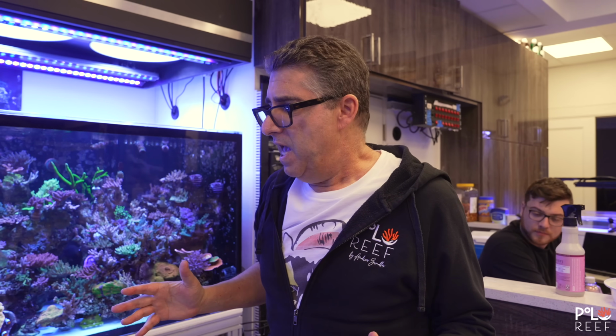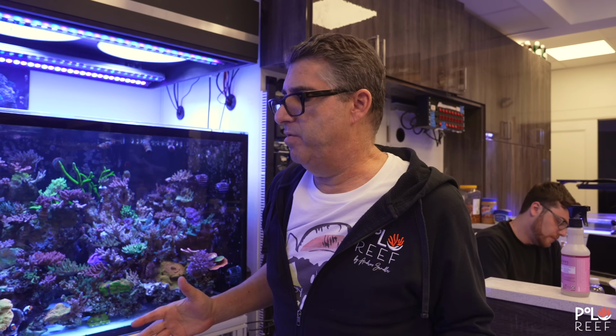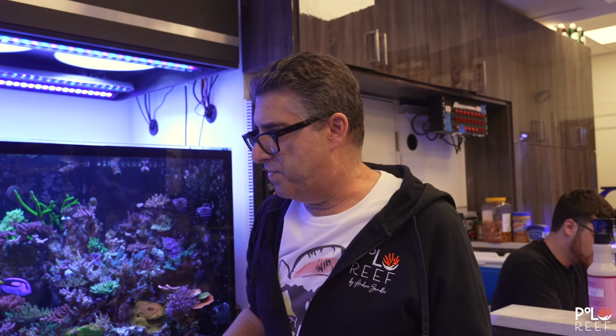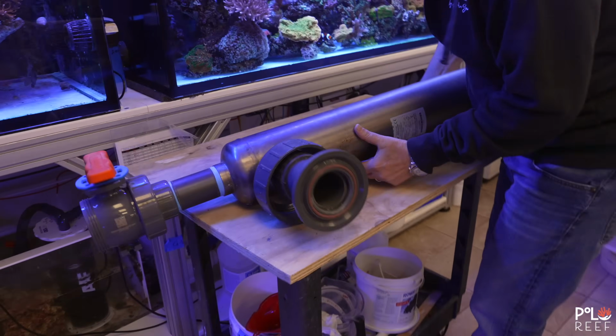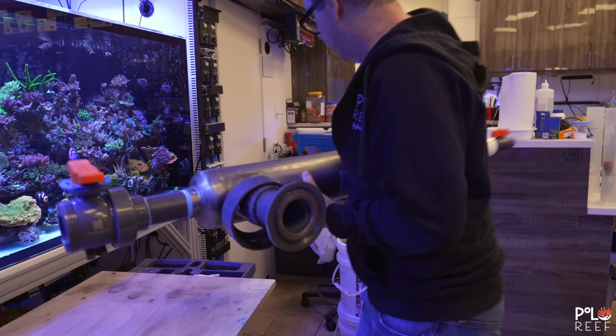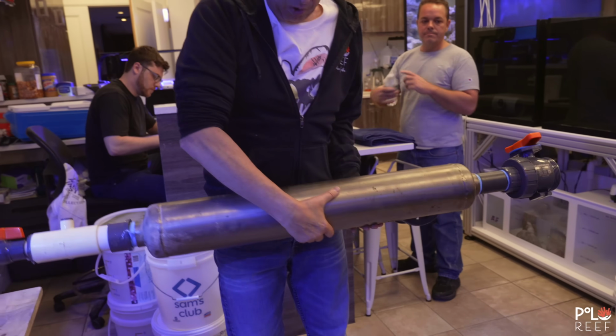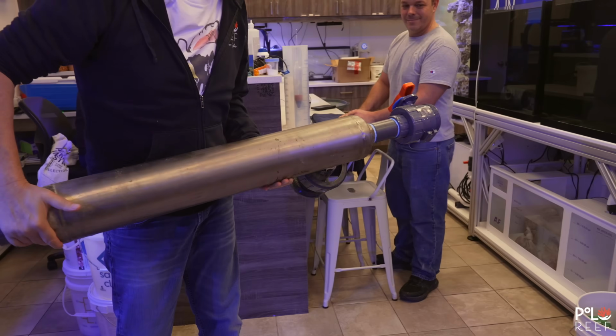We are trying to track down slight elevation in a bunch of metals, and it appears that it's coming from the water vat, but it didn't come from our last test. So we're thinking maybe it's leaking as the water's getting older in the water vat. So the first check is these heat transfer units and the coils in here. We're gonna check the pump too.